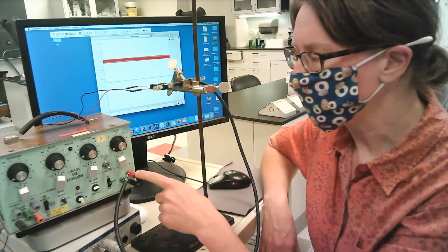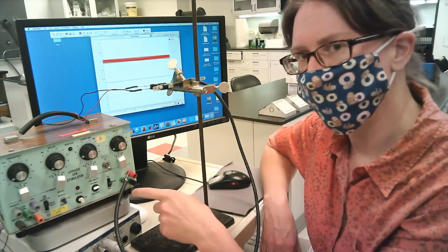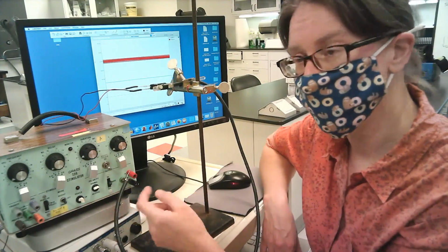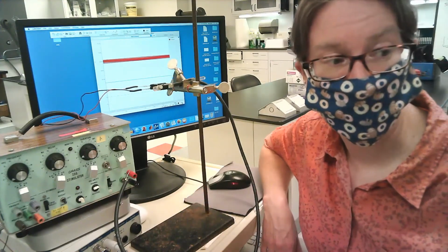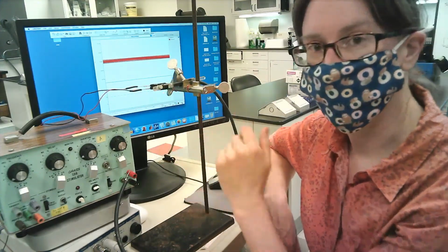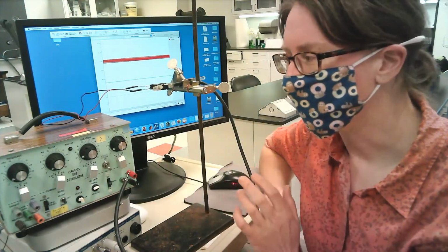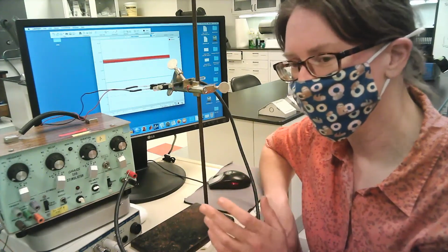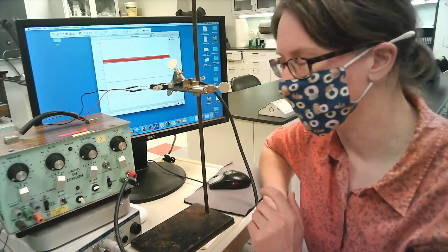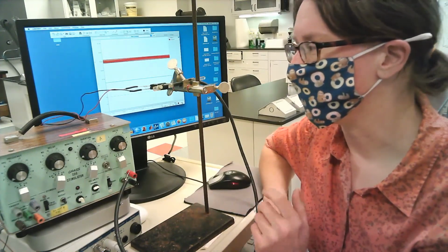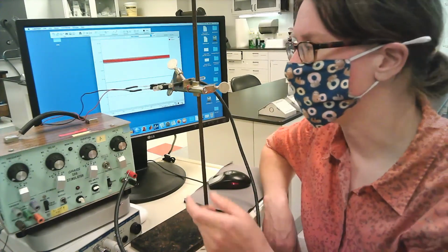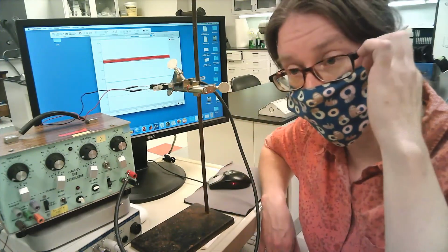So for example, it might be that you have 3 wires and you haven't figured out your stimulating wires versus your ground. And as you just observed, there might be some issues with the contact between the stimulating electrode and the recording needles.